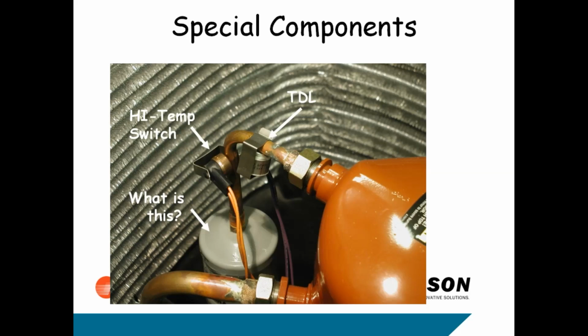Just make sure you never put a dryer on the discharge of a compressor because it melts the desiccant and sends it out into the system, plugs up everything. So that is a muffler. That does not need to be replaced. That can stay in the system unless you have a really, really bad burnout. That really doesn't need to be replaced. So just be aware of that.